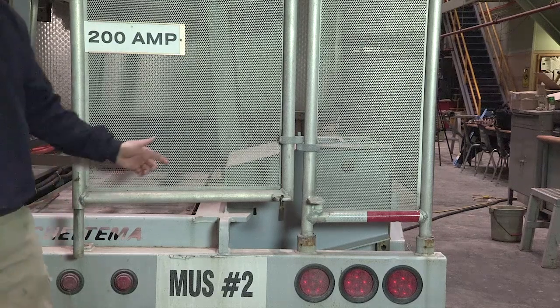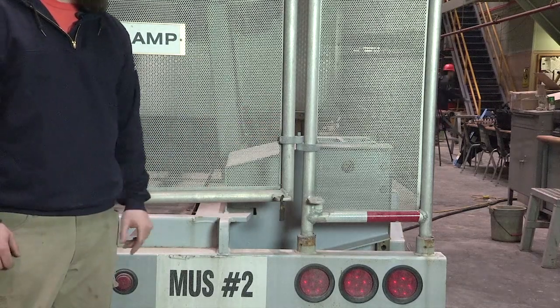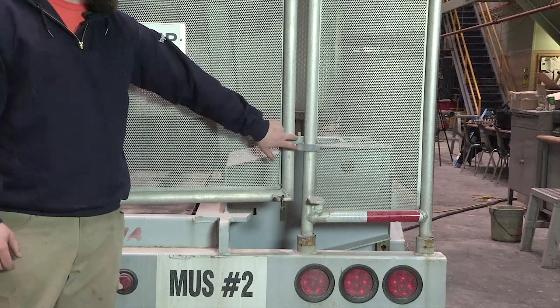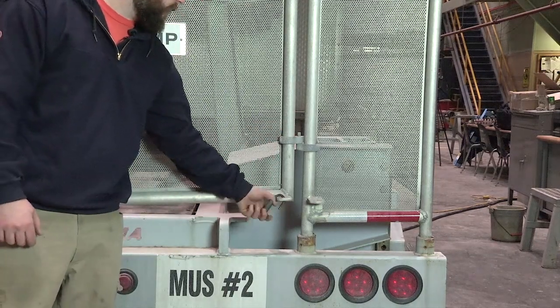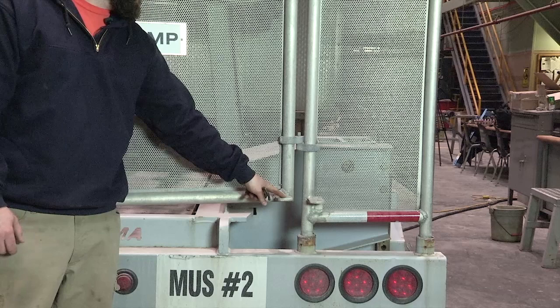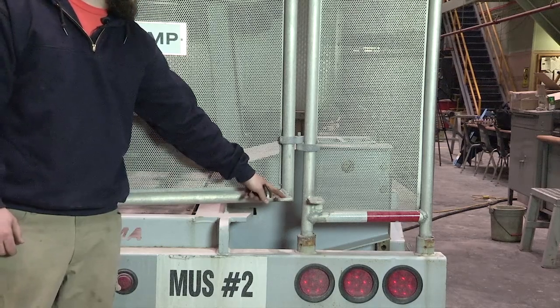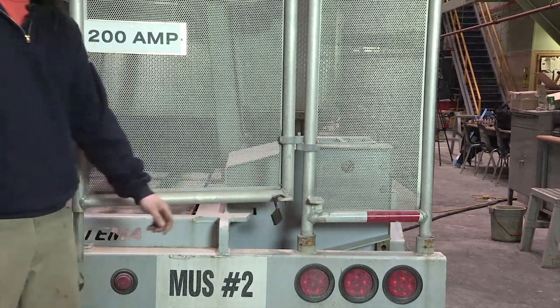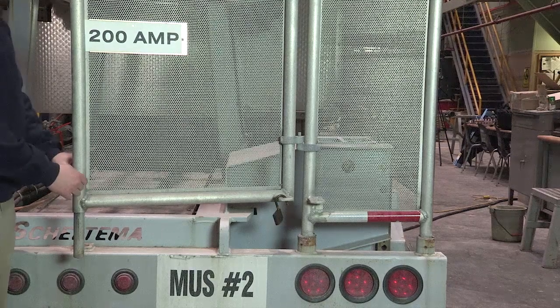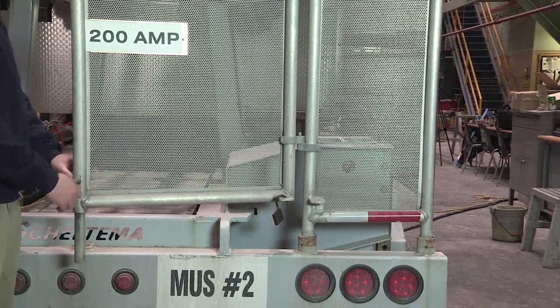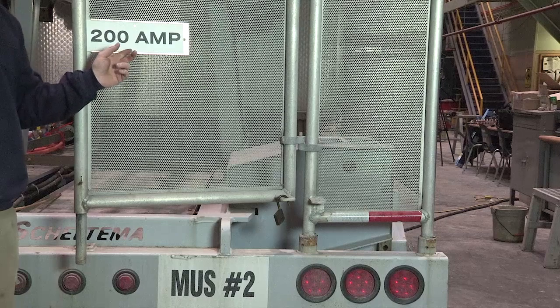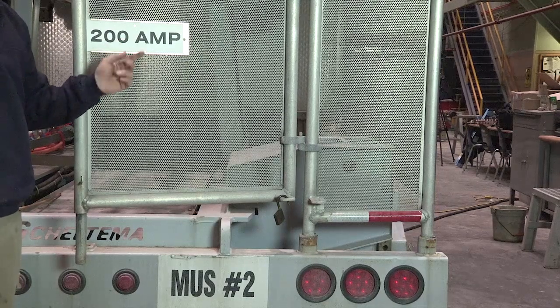Next, we're going to move on to the low voltage side of the MUS, and the first thing you want to do is inspect your gate, just to make sure that everything's operating all right. You want to grease all the hinges. You want to inspect the welds where the lock is going to hold the gate open for yourself when you lock it. Make sure they're good. Just grease anything that's movable, because again, salt and dirt gets in there, and you want to inspect and make sure you have all your fuse amperage signs.